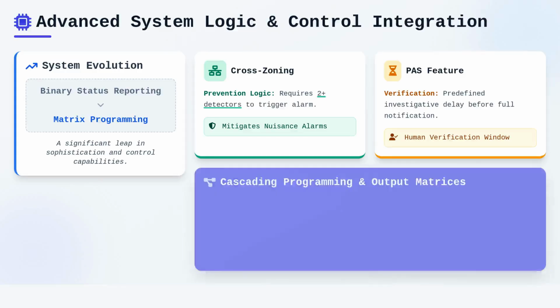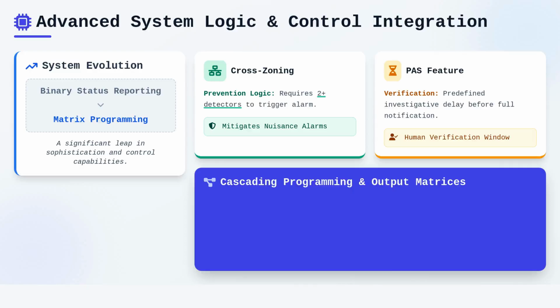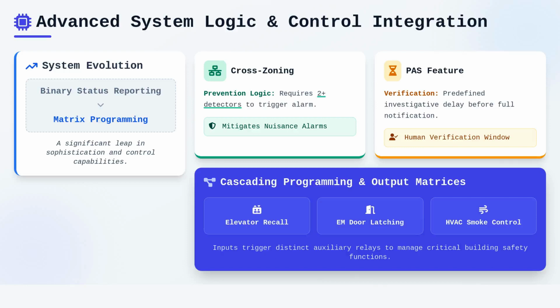This logic is further extended through cascading programming, where various input scenarios trigger distinct output matrices. These matrices dictate the state of auxiliary relays, which facilitate critical building control functions such as elevator recall, the positive latching of electromagnetic door releases, and the shutdown or repositioning of HVAC dampers to manage smoke migration.